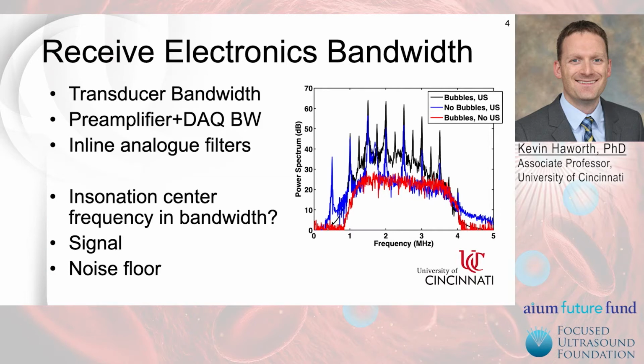The choice of the instrumentation can be adjusted to both maximize the signal recorded, while also adjusting to improve the noise floor for the situation at hand. In this particular power spectrum example, we can see that the hardware is created to have a relatively flat response between approximately 1.5 and 3.5 megahertz, but then the sensitivity drops off pretty dramatically outside of these regions.